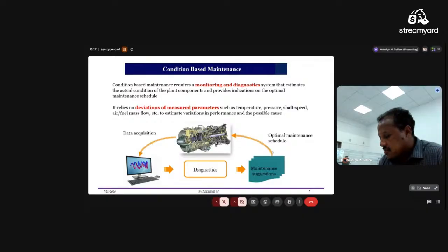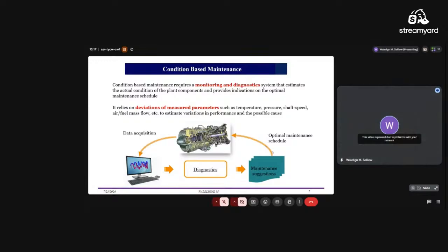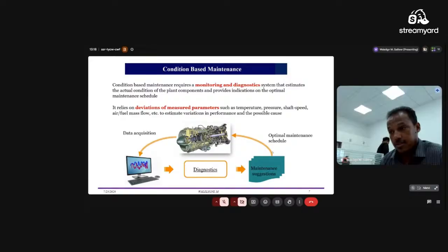So in this presentation, we focused on the third approach, the condition monitoring approach, which is the predictive maintenance type. The idea behind condition monitoring is monitoring the performance of the system, and the maintenance action will be taken depending on the actual performance of the system. It relies on the deviation of measured parameters such as temperature, pressure, shaft speed, and other parameters in the system.